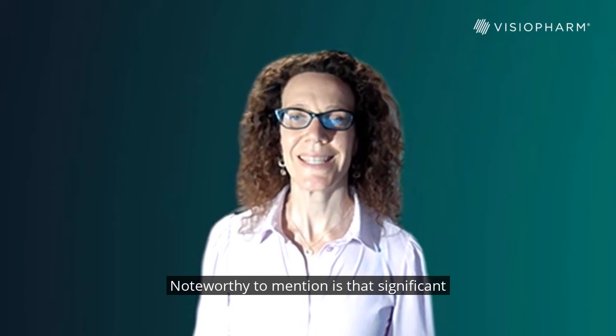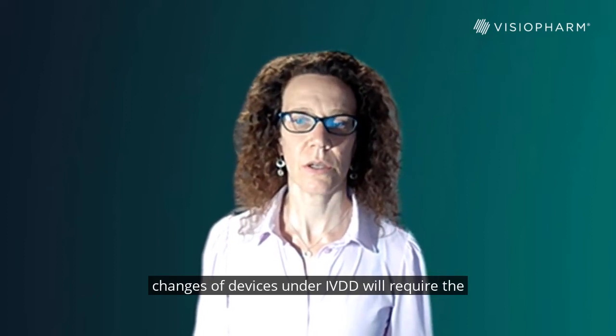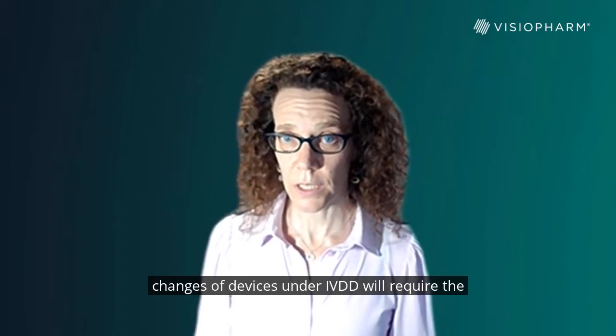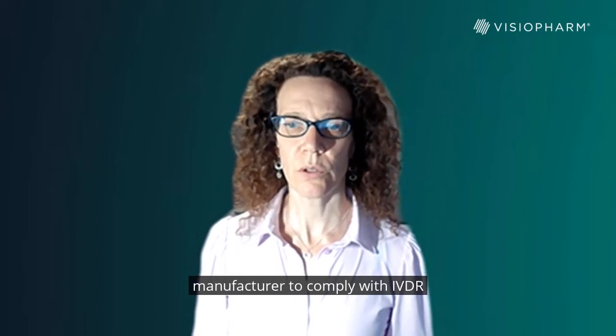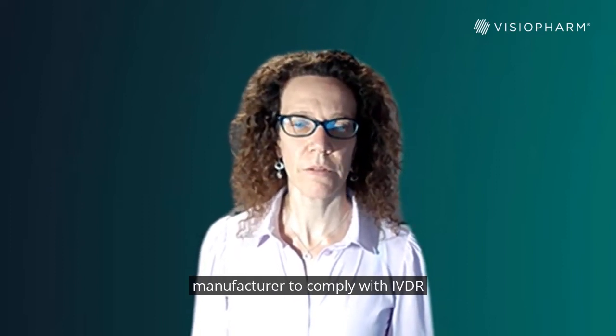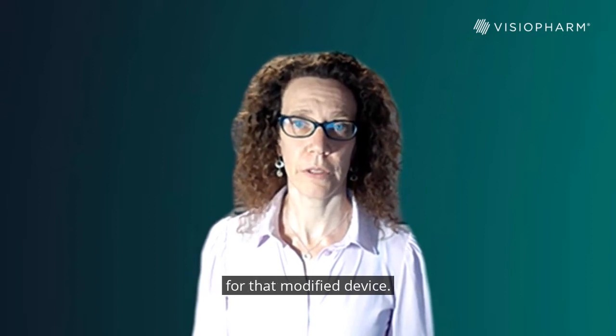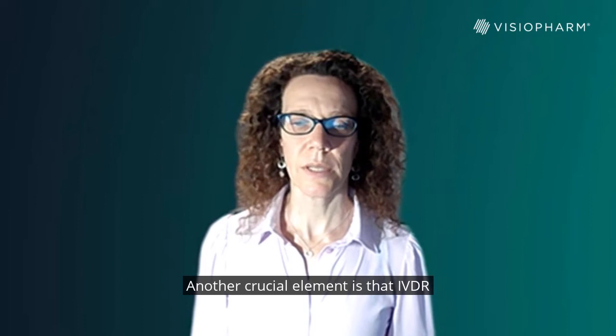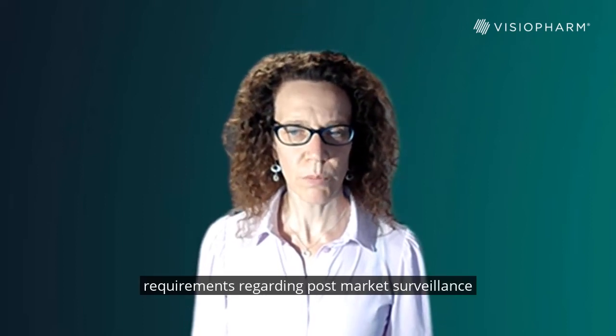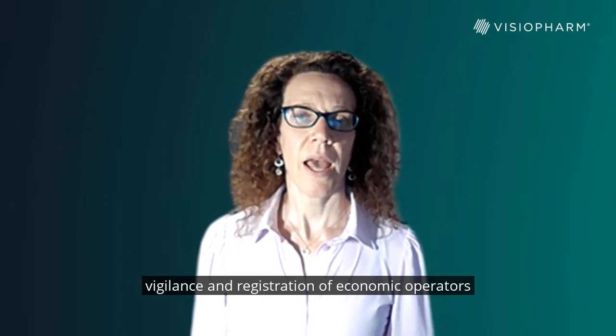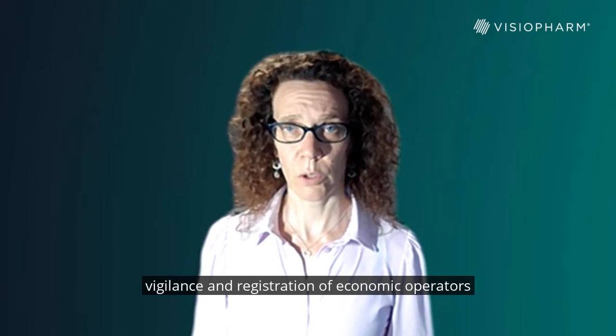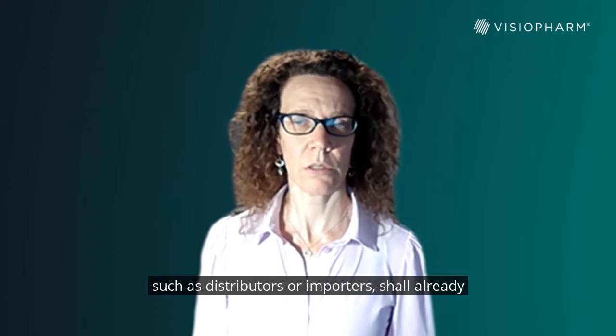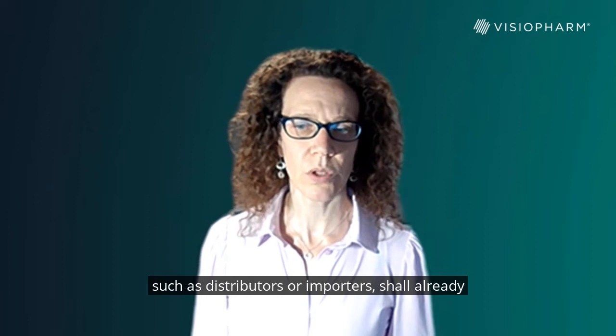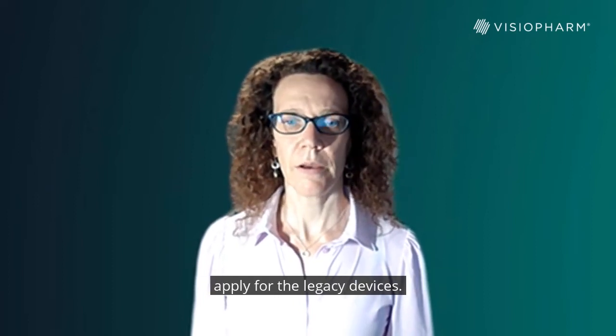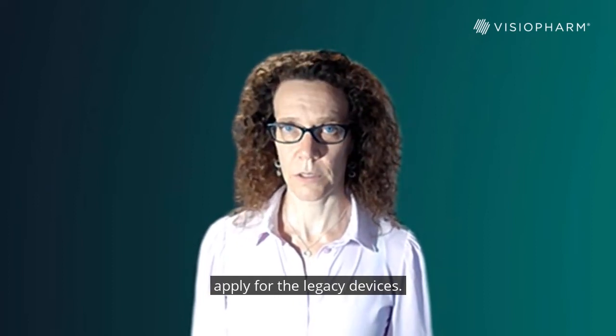Noteworthy to mention is that significant changes of devices under IVDD will require the manufacturer to comply with IVDR for that modified device. Another crucial element is that IVDR requirements regarding post-market surveillance, vigilance, and registration of economic operators, such as distributors or importers, shall already apply for the legacy devices.